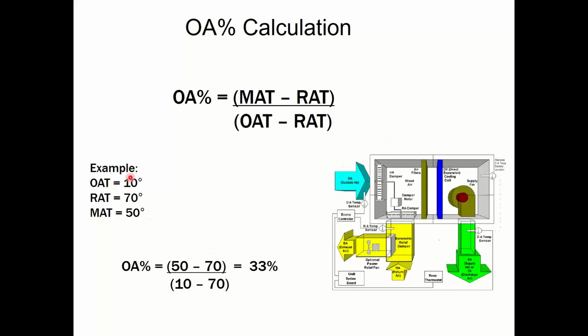So this example is 10 degrees outside with 70-degree return air from the space. And it's a 50-degree mixed temperature. So after the outside and the return mixed, instead of 10 and 70, I had a mixture of 50. Well, mathematically, I can figure out how much came from each. So what's the difference in the mixed air and return air? 20 degrees. What's the difference in the outside and the return air? 60 degrees. So 60 degrees would have been the maximum. If I had gotten this down to 10 degrees, that means all of it came from the outside and none came from the return. So the delta T with max was 60. I got 20. So I have 33%. 33% of my air is coming from the outside air. 67% is coming from the return air.